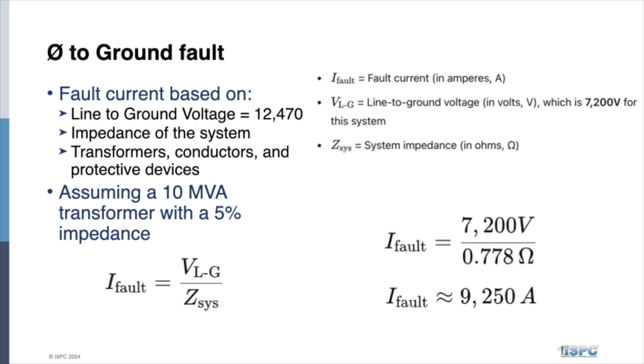So you can see when a fault occurs, the kind of current we just said your 2-aught temporary grounds are good for 300 amps, right? Well, they're not going to sustain a 9,000 amp fault. You're going to vaporize them, right? So the key is the grounds need to be able to carry enough current to allow that 2 to 3 cycles to trip those protective relays off, right? That's the key, okay?